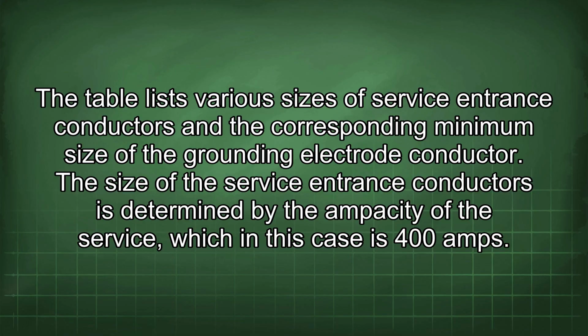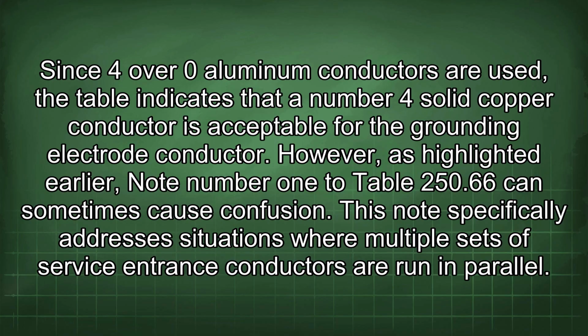The size of the service entrance conductors is determined by the ampacity of the service, which in this case is 400 amps. Since 4/0 aluminum conductors are used, the table indicates that a number 4 solid copper conductor is acceptable for the grounding electrode conductor. However, as highlighted earlier, note number 1 to Table 250.66 can sometimes cause confusion.